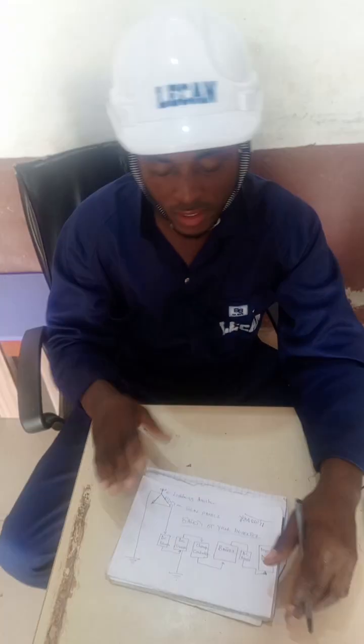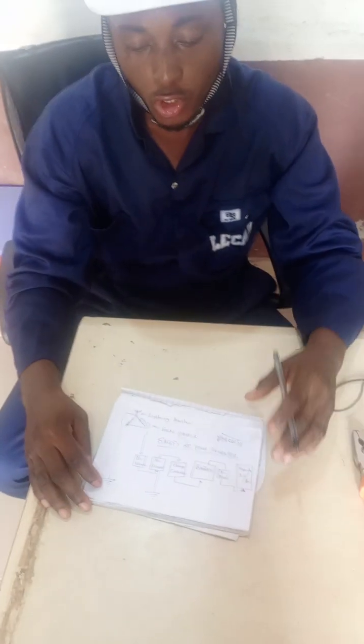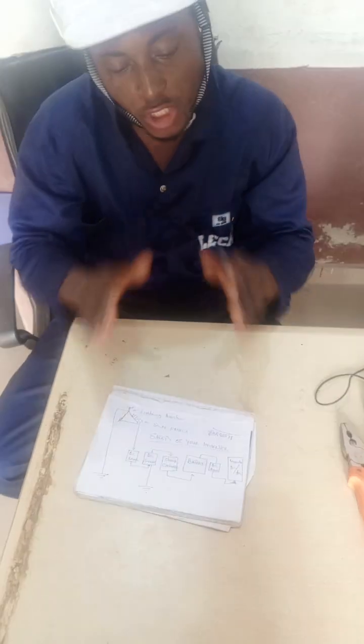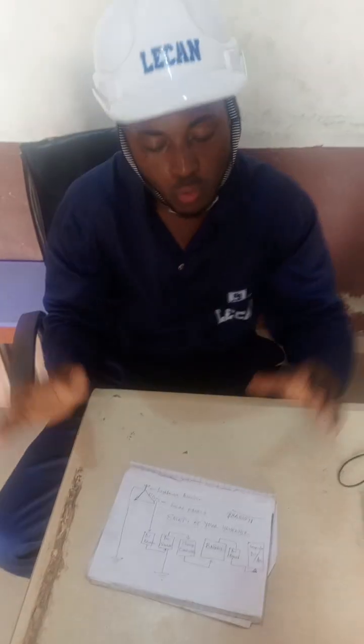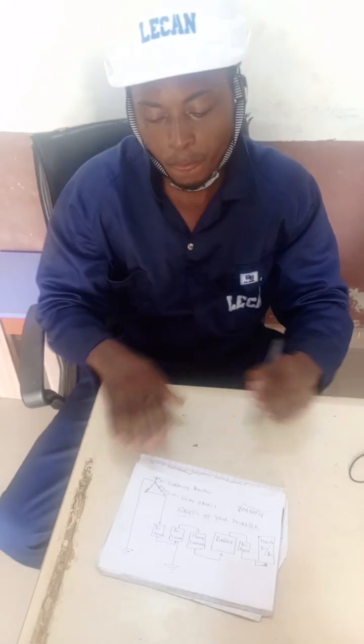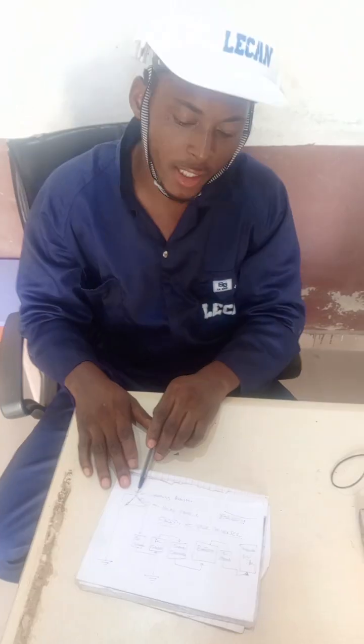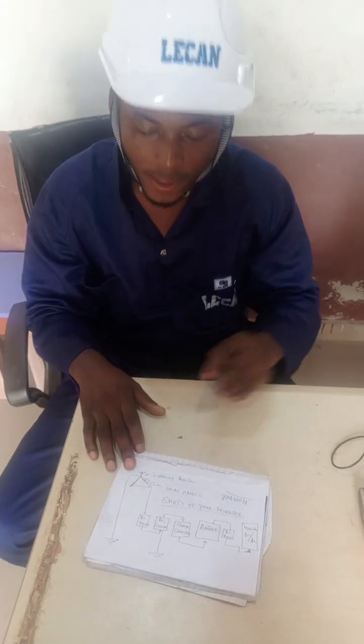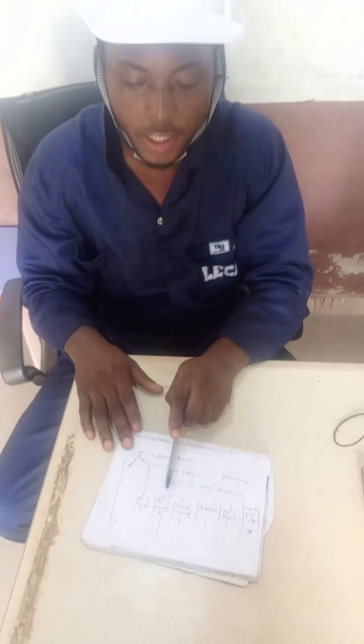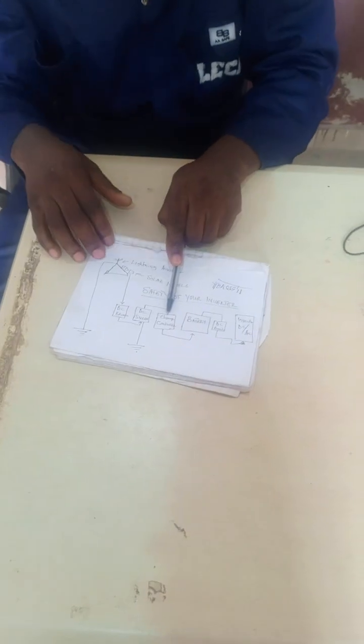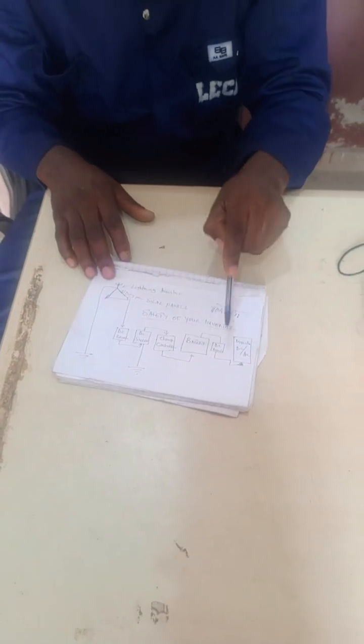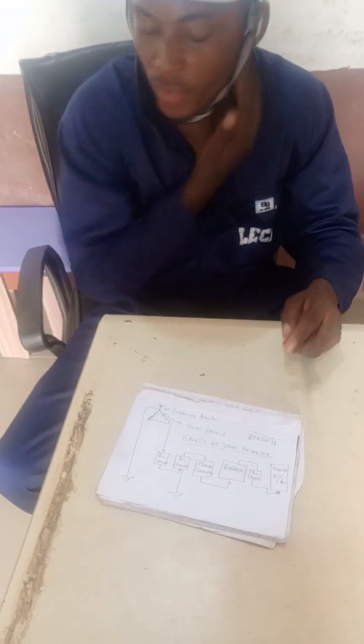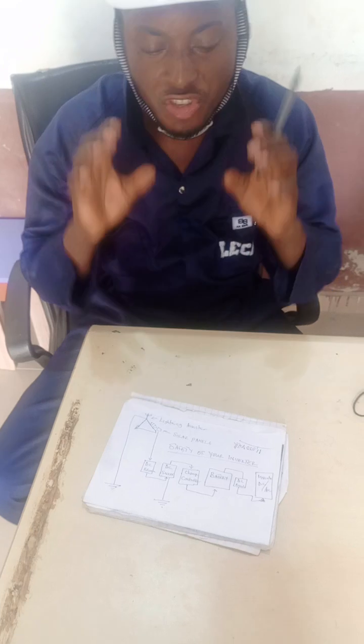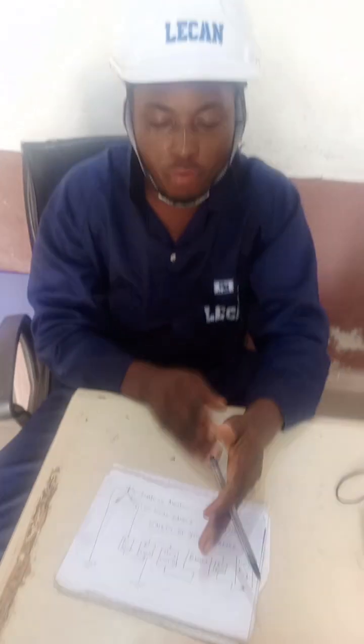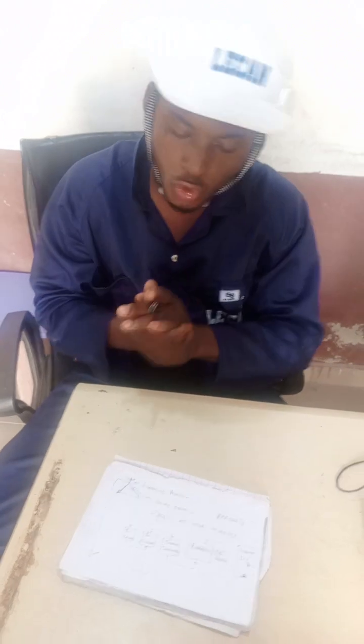Safety of your inverter. And before me now, I have a sketch on how your inverter system is supposed to be designed to charge your battery and for your inverter to work safely. Now, on this sketch, you are going to see a spike here. This spike is what we call the lightning arrestor. Then we have the DC breaker, the surge protector, the solar charge controller, the battery, the DC breaker, then your inverter. Now, this arrangement is going to save the life of your inverter, save the life of what? Of your battery and even your charge controller.